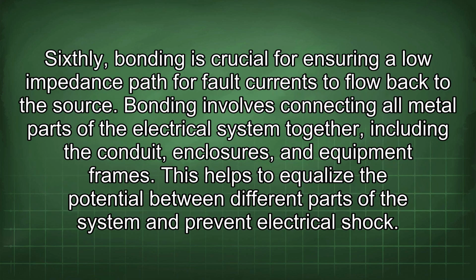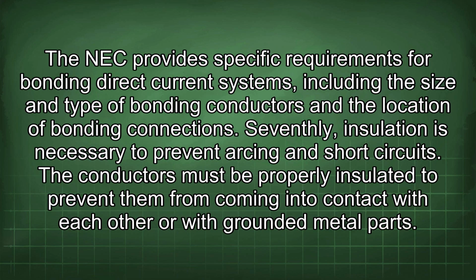Sixthly, bonding is crucial for ensuring a low impedance path for fault currents to flow back to the source. Bonding involves connecting all metal parts of the electrical system together, including the conduit, enclosures, and the equipment frames. This helps to equalize the potential between different parts of the system and prevent electrical shock.